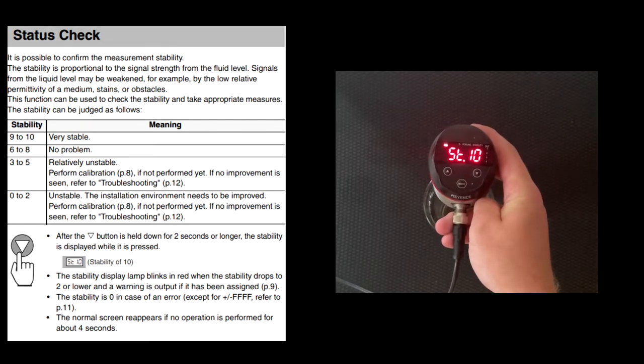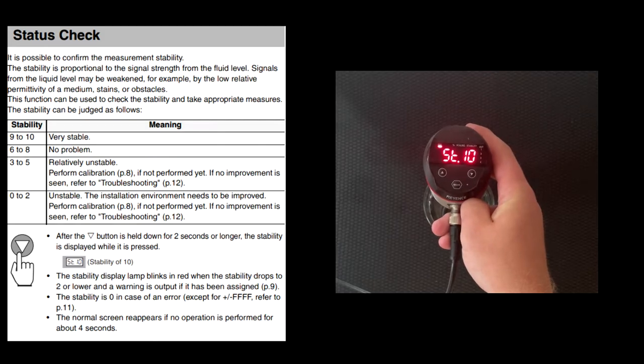Now that you've successfully calibrated and zero shifted the FL, it's time to confirm that we have good stability. To do this, on the main display, you're going to hold the Down button for two seconds or more until ST and a number, or a digit, is displayed. 9 to 10 is very stable, and that means you performed everything correctly.